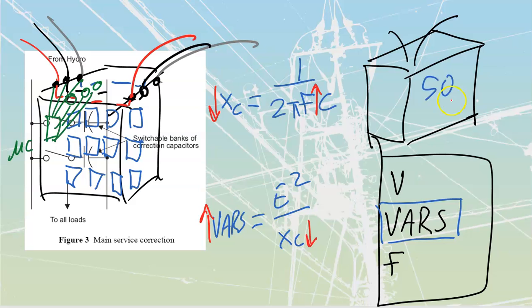But we still wouldn't want to necessarily do it. First of all, this thing has been engineered for 50 hertz. 50 hertz just means it's a slower back-and-forth movement. The dielectric, the amount of heat, all of that has been based on those individual orbitals going back and forth 50 times a second. Now we're going up to 60 times a second. You change from 50 reps of anything in the gym to 60 reps, you feel it — so does the dielectric inside of here.